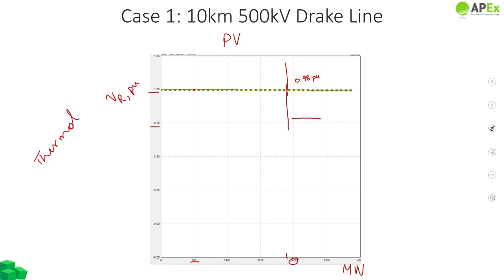On our screen now is the second case, where the transmission line on the same Drake conductor is 100 kilometers. What we can see here is that the whole picture has changed drastically. We saw that our thermal limit was at 2700 megawatts, which would be somewhere here, but our voltage has collapsed way before it.